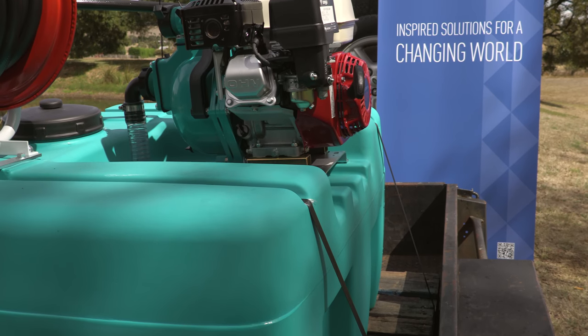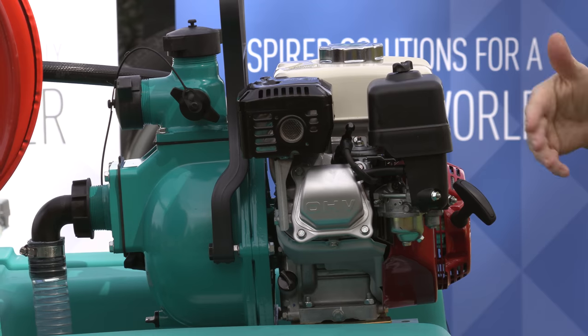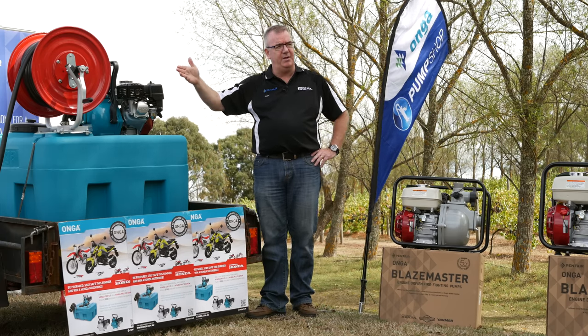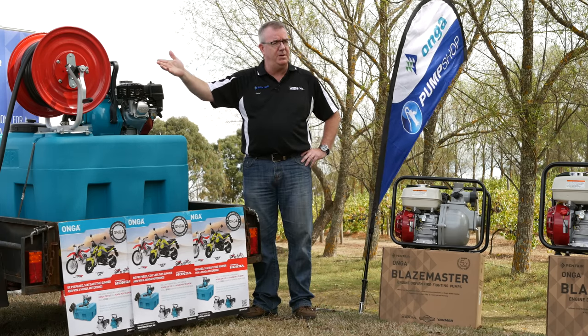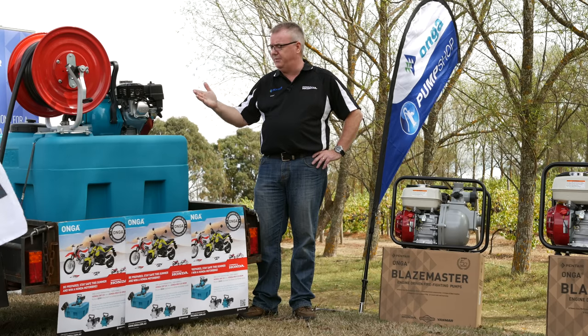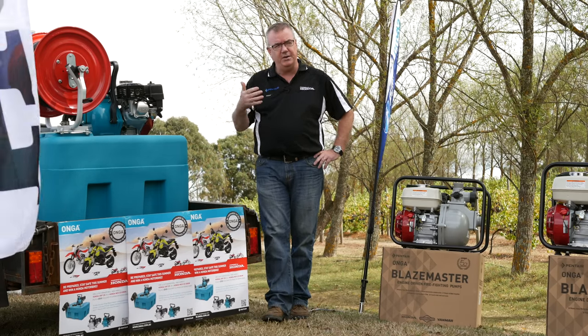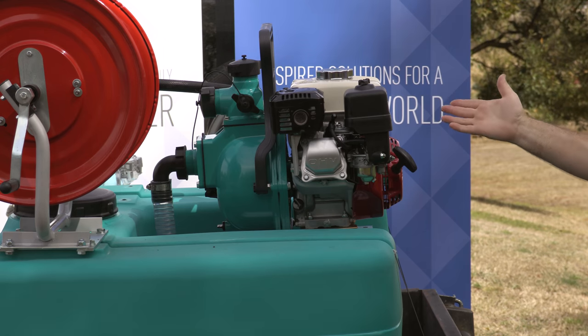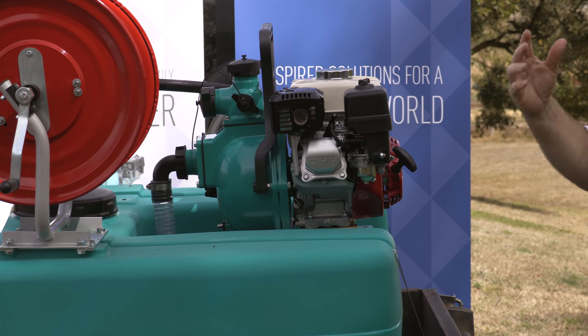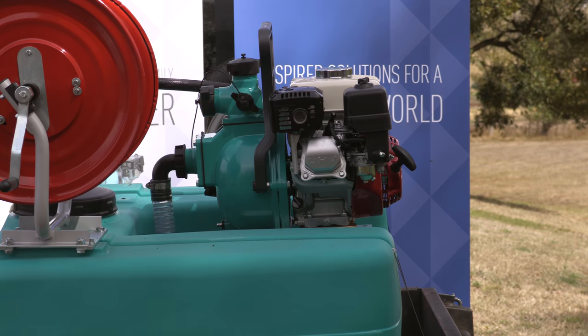The engine coupled here drives a single-impeller firefighter pump. This type of product can move up to 500 litres of water a minute, but with a 400-litre tank you need to manage your flow rates, which is why we use a 20mm fire hose — we don't want large flow rates consuming your water quickly in a fire situation. The pump is coupled to a Honda GX200 motor. This morning the motor was brand new; we applied oil and fuel, gave it three pulls, and it started — that's the reliability we're looking for.